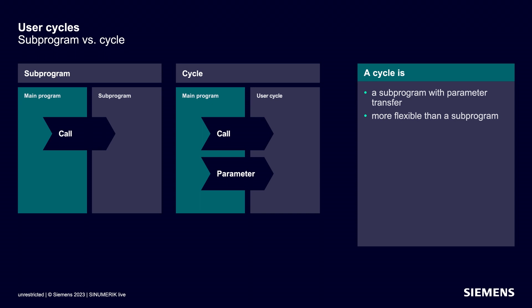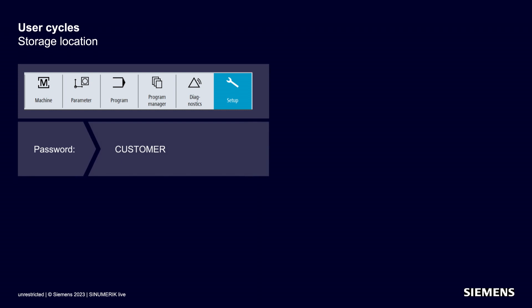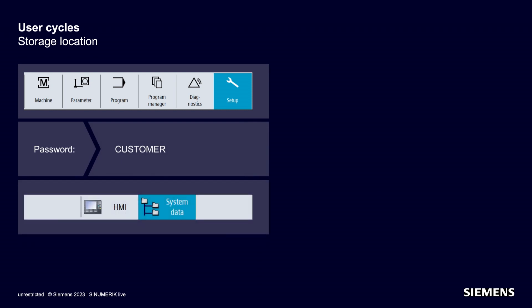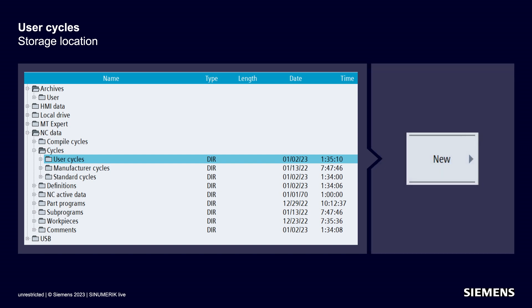The program code of these tested program sequences does not have to be accessible to everyone in the program manager. User cycles are not found in the conventional storage structure for CNC programs. That's why we switch to the Commissioning operating area, enter the password 'Customer', and then switch to the System Data input screen. From here, we navigate via the NC Data folder to Cycles, then to User Cycles, and press New to assign a name.